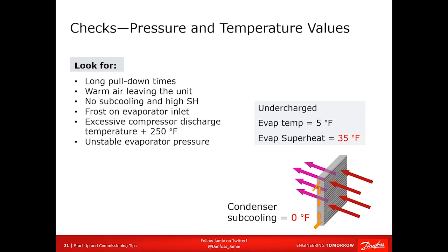What isn't so obvious is the stuff you have to go measure. We've already talked about it. No subcooling, high superheat, low evaporator temperature. With an AC system, you'll have frost or may have frost on the inlet only of the evaporator because you're operating below 32 degrees. You're going to have excessively high suction temperatures, excessively high superheat, and your discharge temperature could easily be over 250 degrees. This is a danger zone.